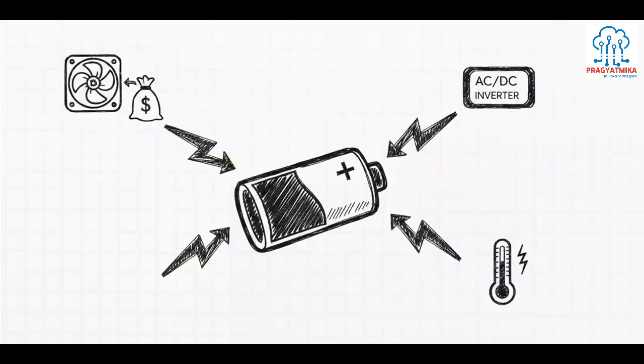So where exactly does that 6 to 12% actually go? There is a massive hidden cost here. Part of it gets lost to the battery cell's own internal resistance, sure. But more importantly, it's lost to the auxiliary systems required to run the battery itself. The inverters that convert alternating current from the grid into direct current for the battery cause a loss. And ironically, the battery literally consumes its own potential profits just to power its massive HVAC units, cooling fans, and safety equipment so it doesn't overheat during operation.